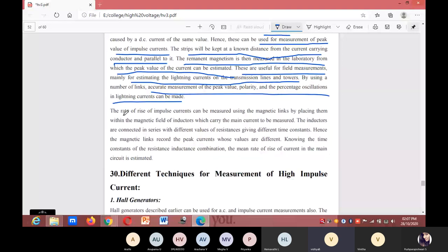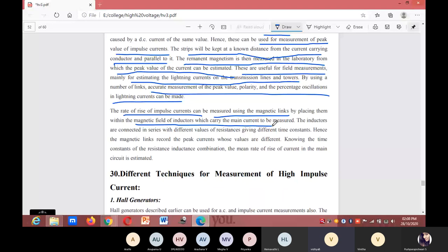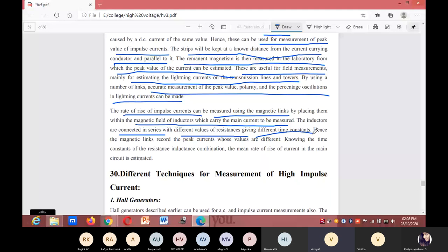The next topic is the rate of rise of impulse currents. This can also be measured using magnetic links by placing them within the magnetic field of inductors which carry the main current to be measured. The inductors are connected in series with different values of resistors, which give different time constants. The magnetic link records the peak current, whose values are different.